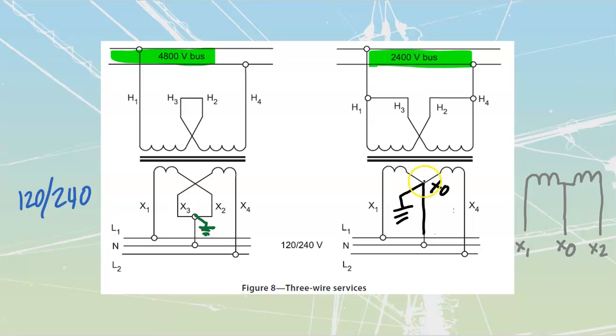In most cases as well, the neutral will be bonded to the frame, and you're going to have to remove that. But we'll cover that inside of grounding and bonding later on. For now, just be aware that a neutral component can exist. We don't always make it like we do over here; sometimes it already exists, and it's designated with that X0.